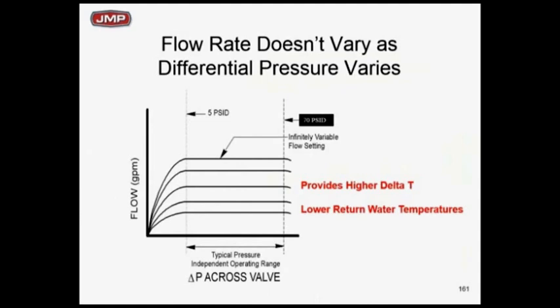Let's take a look at this again. As long as I stay, just like a flow limiter, within that straight line, with the minimum pressure required to make it work at 5 pounds, and in this case the max is 70, as long as I stay in that range across my two-way PIC control valve, I'm going to maintain flow rate. I'm going to give you the highest possible delta T. I'm going to give you the highest possible efficient system with a pressure independent control valve.